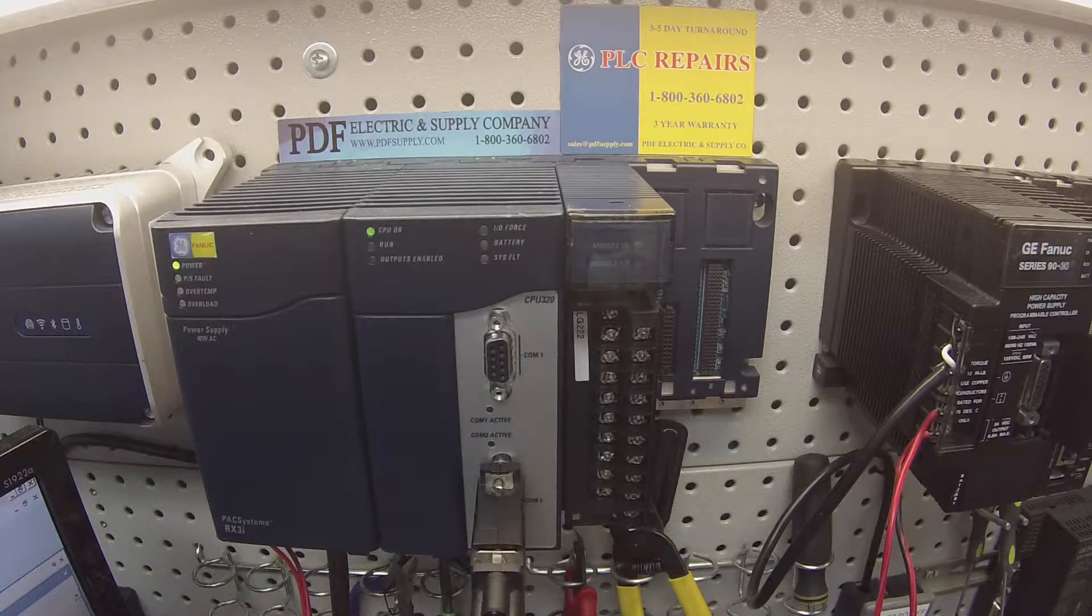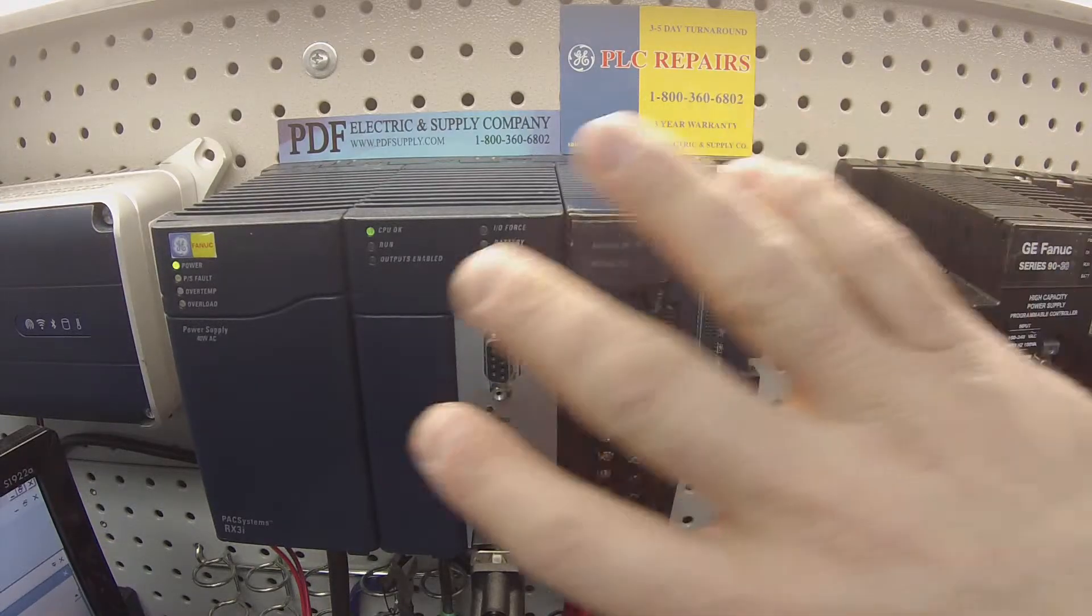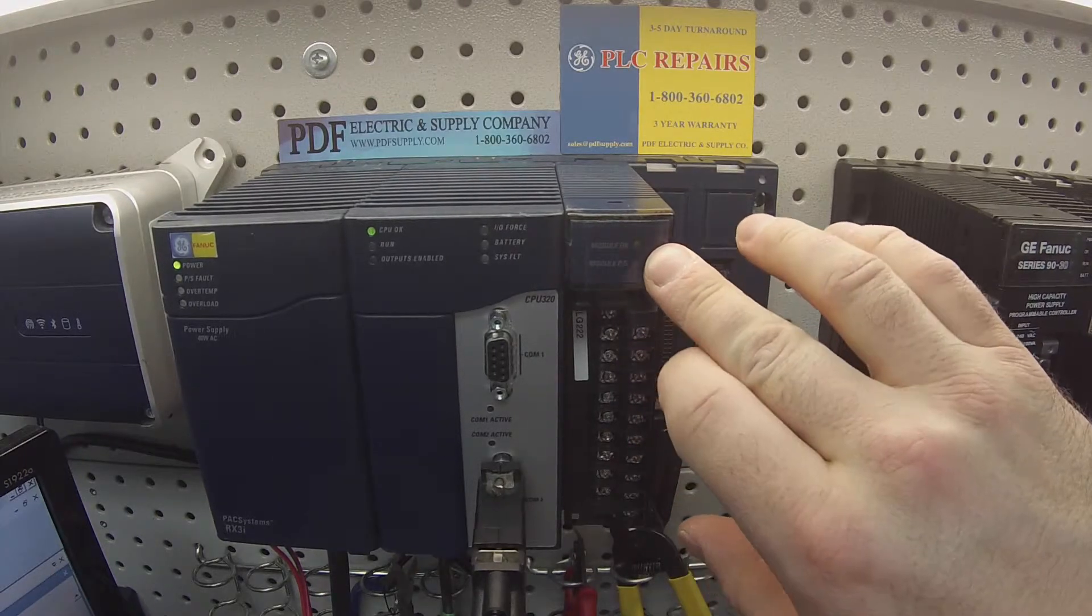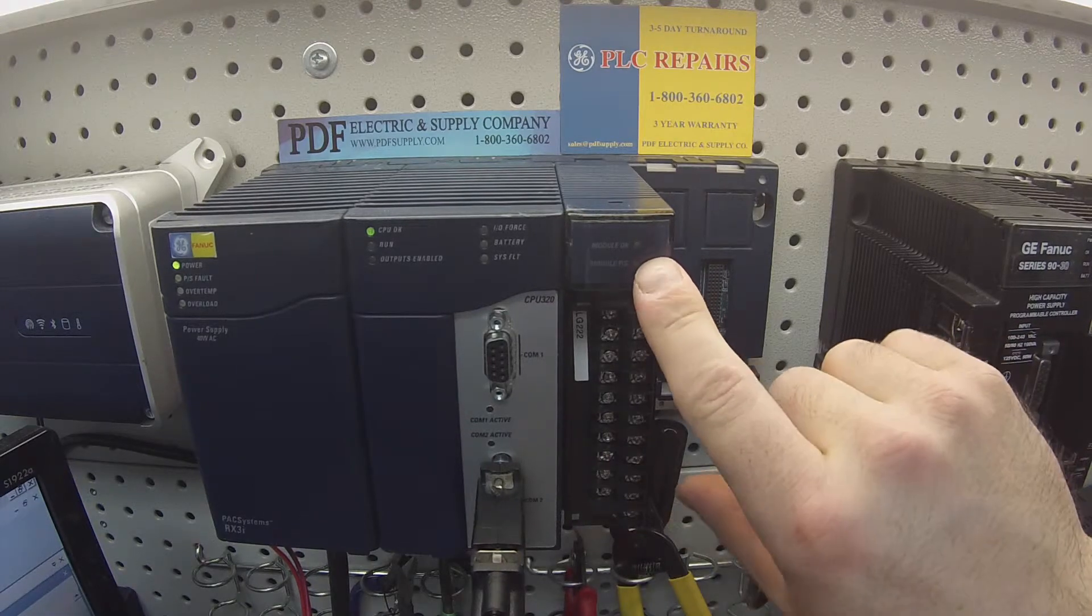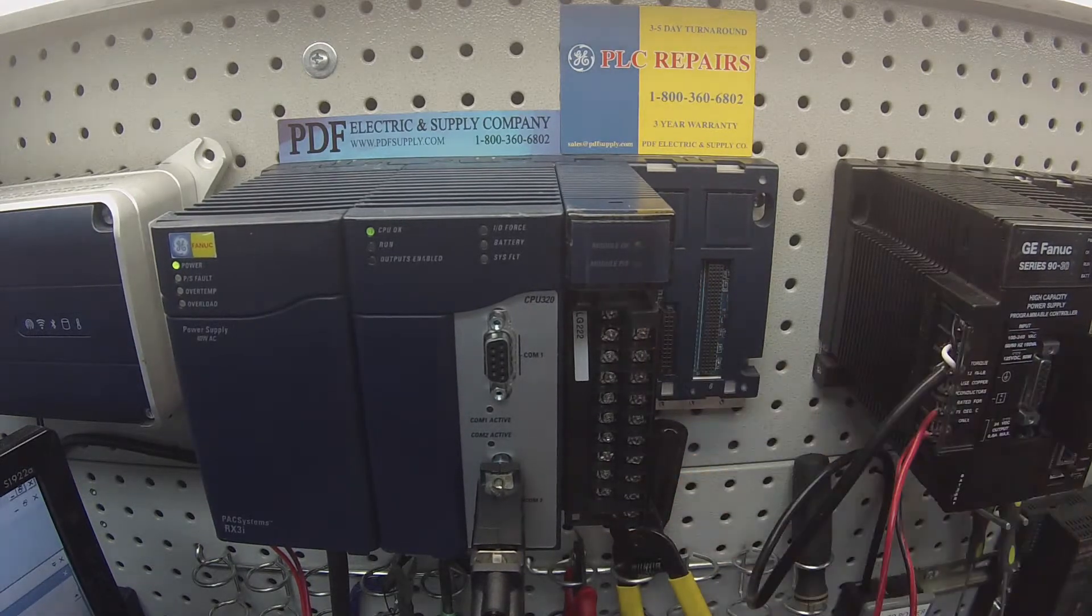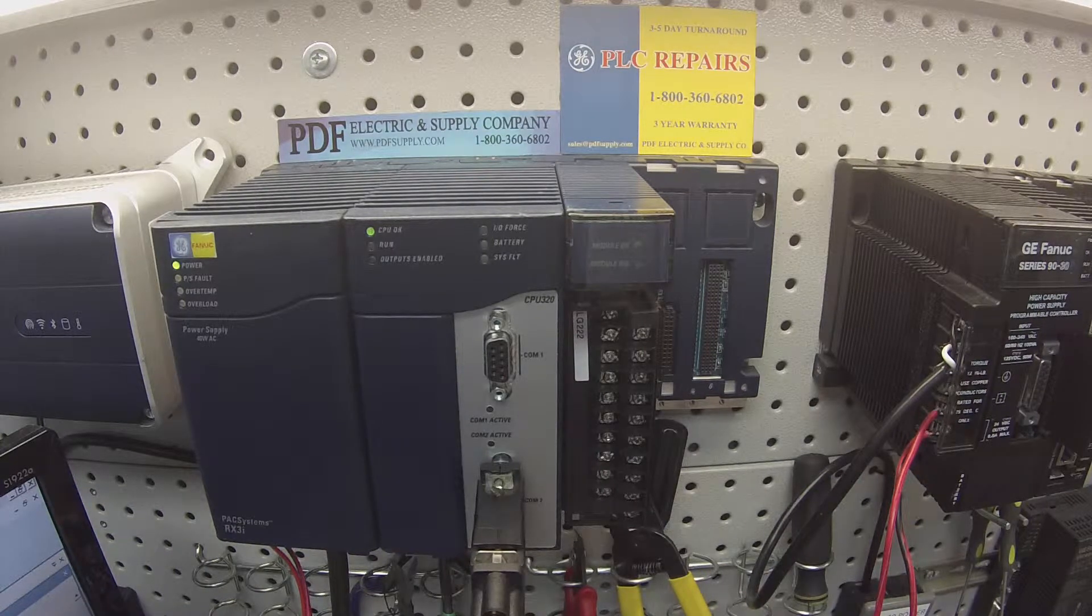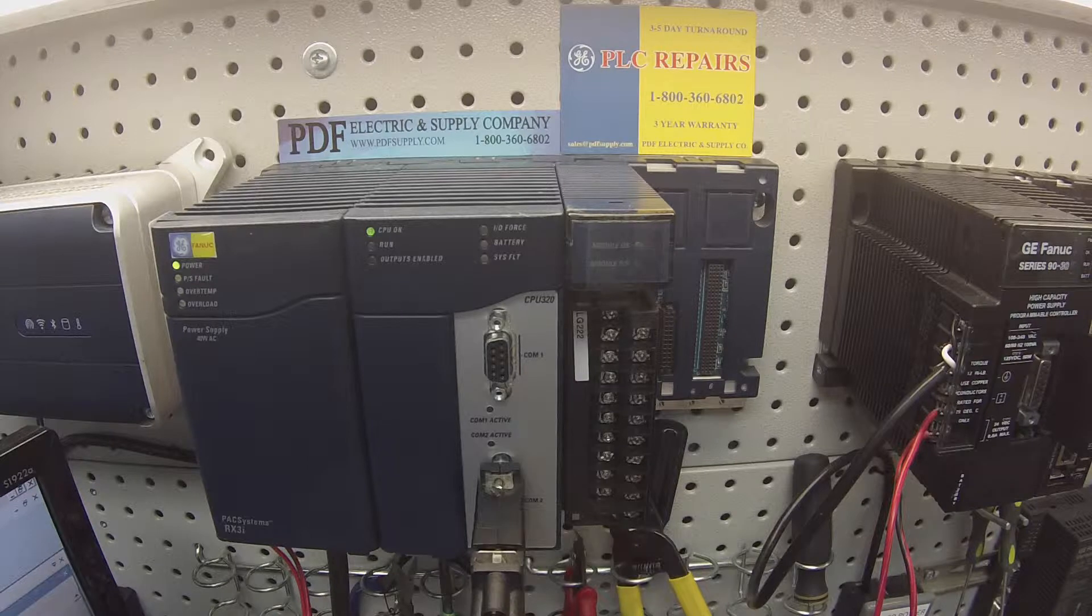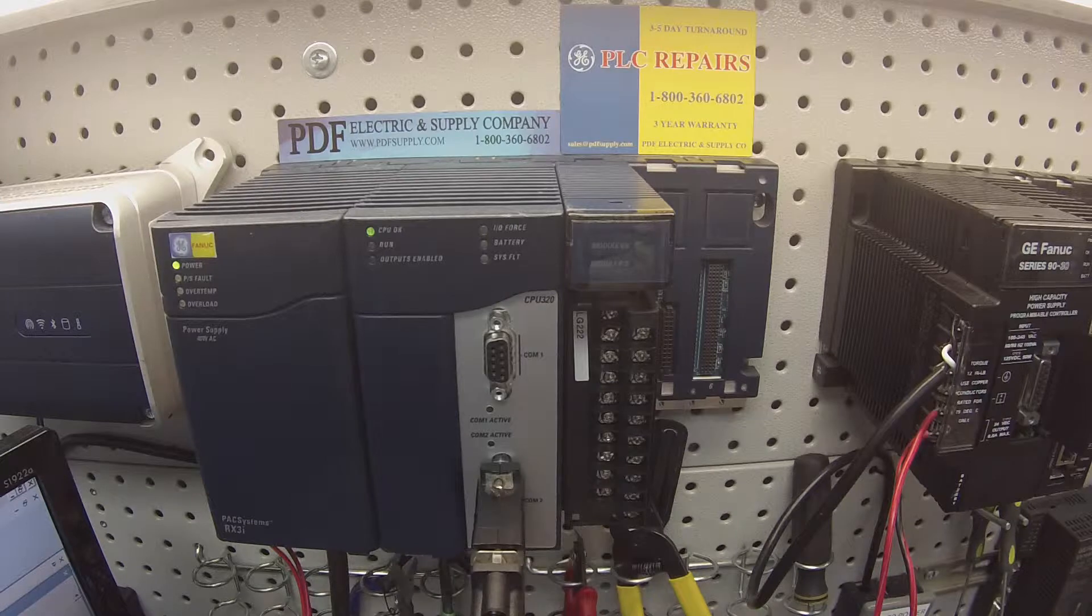A couple things about this card: when you have the system powered up the way you see it here, you should have a module OK light on. When it goes through the self diagnostic, it should be green here or at least blinking green. If you don't have any light on, that means there's some sort of problem with the card and you'll need to either replace it or repair it.